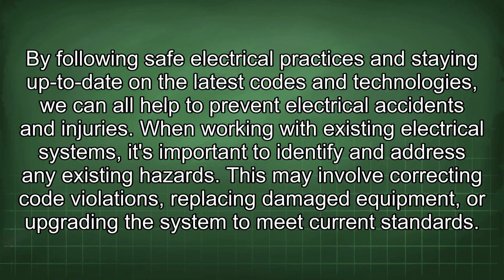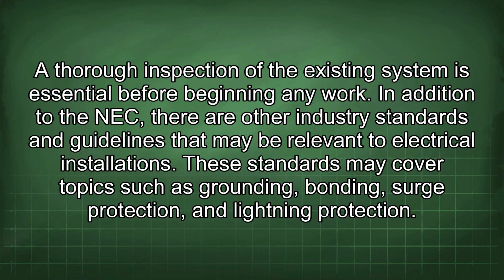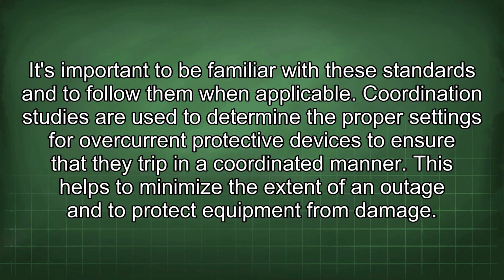When working with existing electrical systems, it's important to identify and address any existing hazards. This may involve correcting code violations, replacing damaged equipment, or upgrading the system to meet current standards. A thorough inspection of the existing system is essential before beginning any work. In addition to the NEC, there are other industry standards and guidelines that may be relevant to electrical installations. These standards may cover topics such as grounding, bonding, surge protection, and lightning protection. It's important to be familiar with these standards and to follow them when applicable.